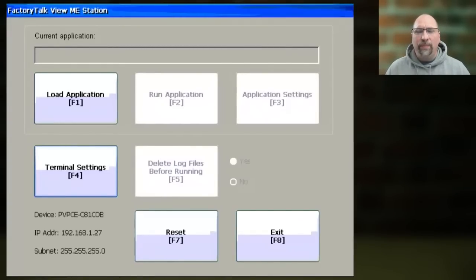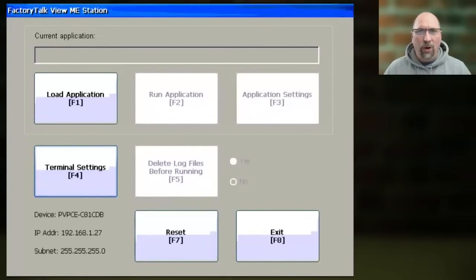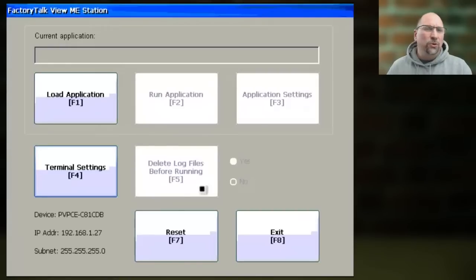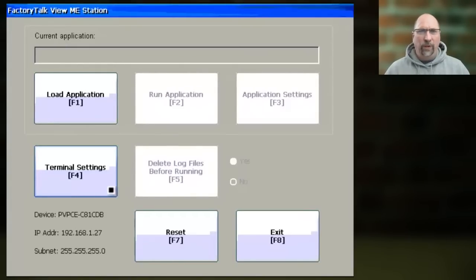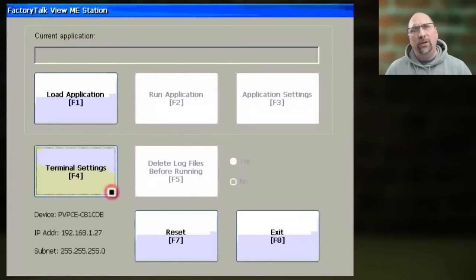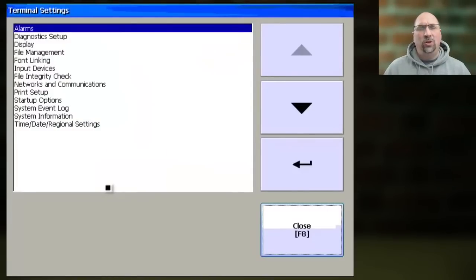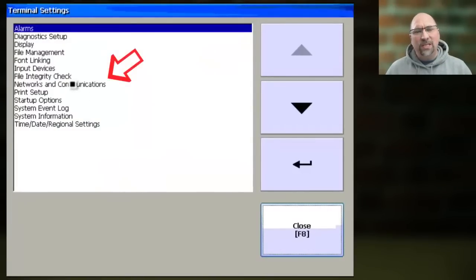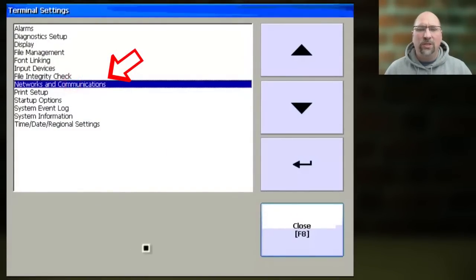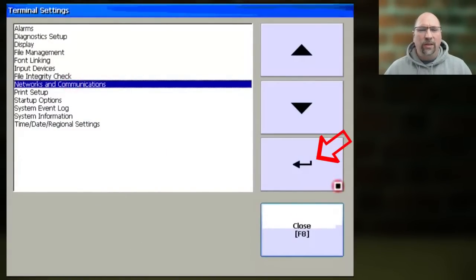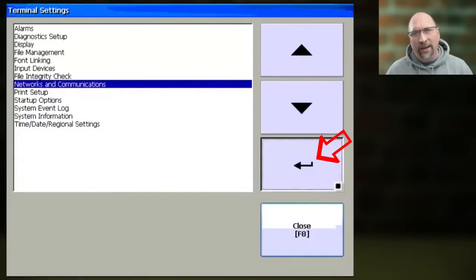Now the first step is to start at the configuration menu of the PanelView Plus, which I showed you how to get to in a previous video. From there, you want to select Terminal Settings, and then from that menu, you want to select Networks and Communications, and then go ahead and select Enter.